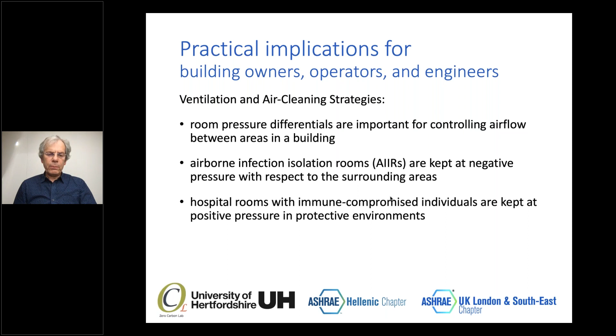This is how it works. So if you have an airborne infection isolation room on the left, you would put that onto negative pressure simply by running the fan that supplies that room slightly slower if it's a supply fan, or slightly faster if it's an extract fan. The opposite occurs in the surrounding rooms, where you need to achieve positive pressure. A pressure difference of several pascals, like 3-4 pascals, will do the job very nicely.